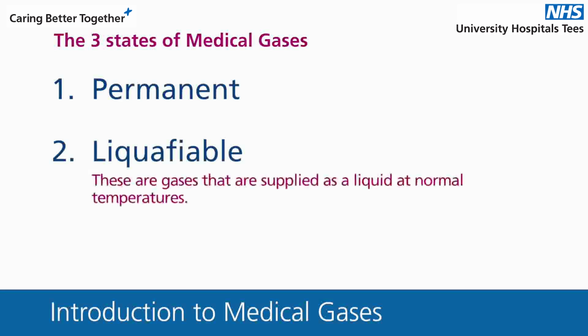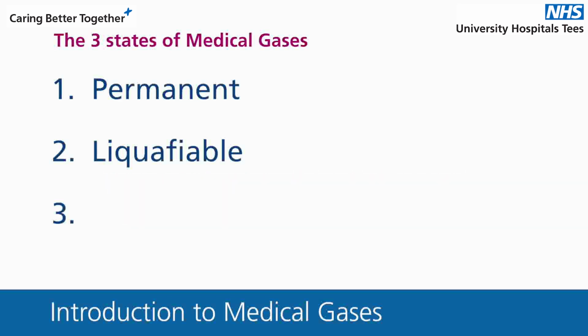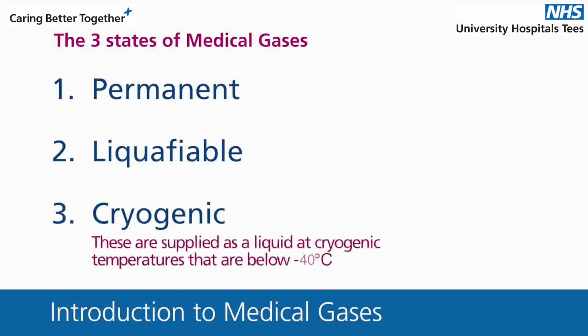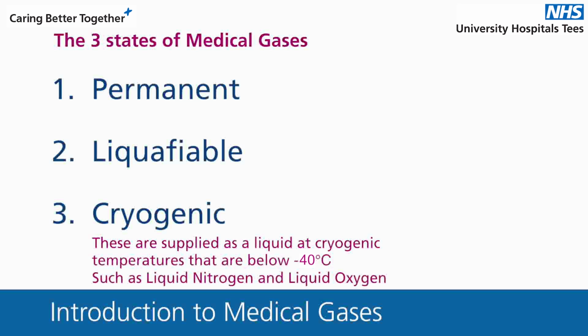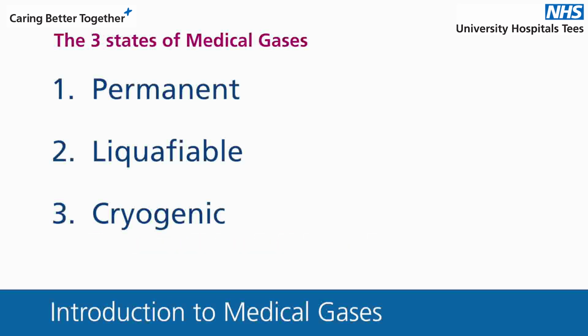Liquefiable. These are gases that are supplied as a liquid at normal temperatures. For example, nitrous oxide and carbon dioxide. Cryogenic. Gases supplied as a liquid at a cryogenic temperature, that is, below -40 degrees Celsius. For example, liquid nitrogen and liquid oxygen.